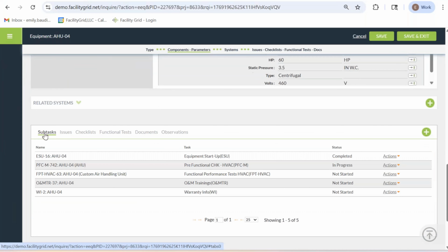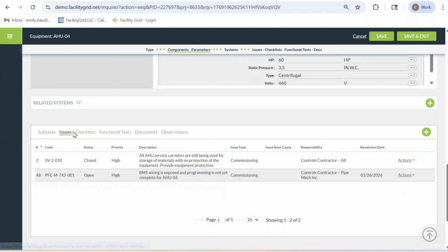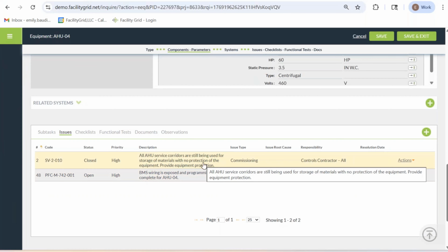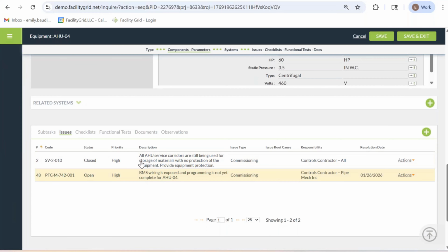Down at the bottom is where I get my true record of readiness for this asset. So if I click the subtask tab, I can see what's been done and what hasn't for this asset. I notice it's been started up and the pre-functional checklist is in progress. Then if I click over to issues, I can see if there are any outstanding issues that may be holding up moving forward with this asset. It looks like I have an open issue regarding BMS wiring that is exposed, and that needs to be closed out before I can move on.